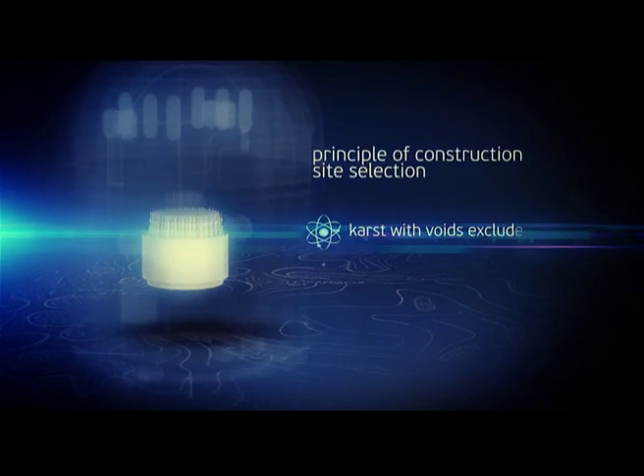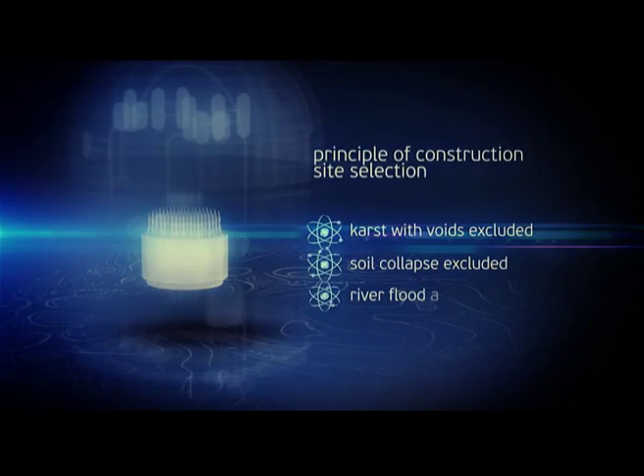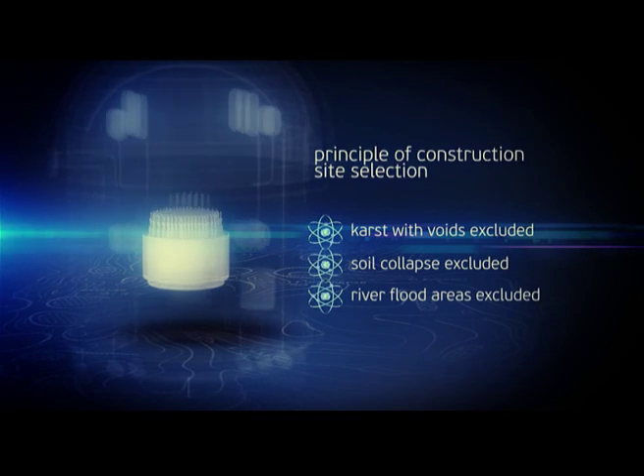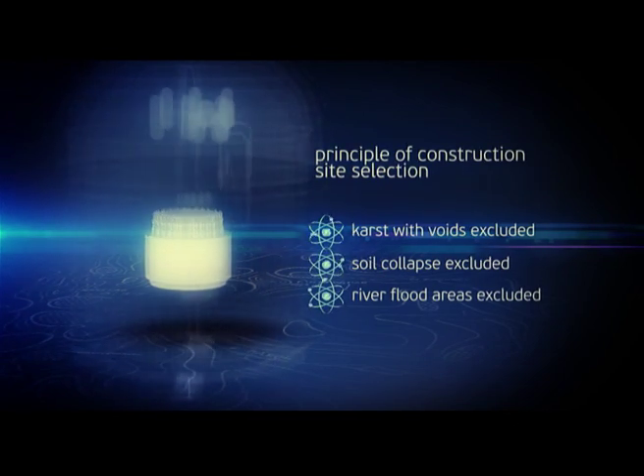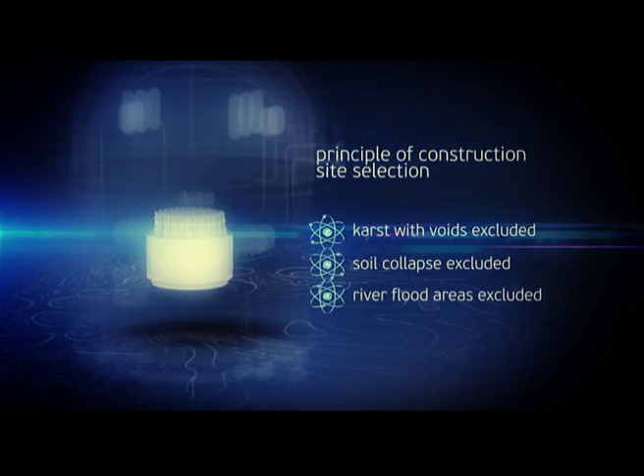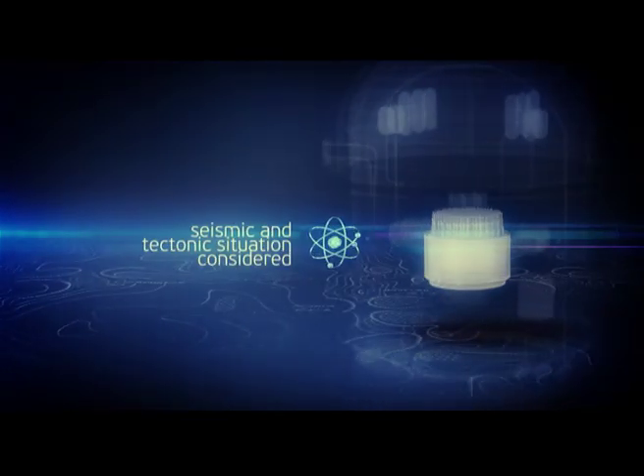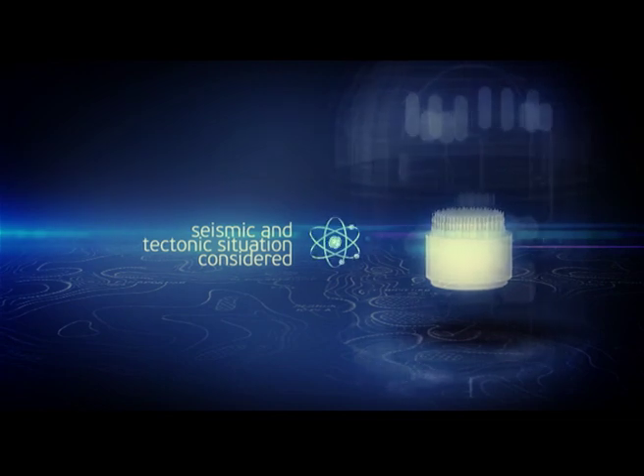One more element of the plant safety is the principle used for selection of a construction site. The site is selected by more than 20 parameters. Sites featuring karsts with voids, soil collapse, and river floods are excluded. A prime focus is on seismic and tectonic features of the plant hosting region.